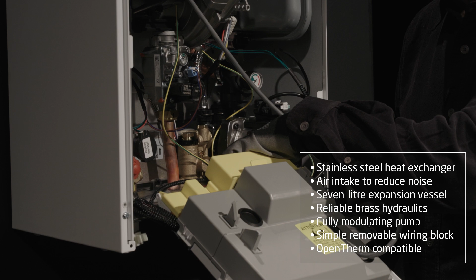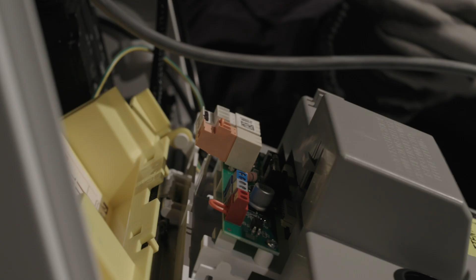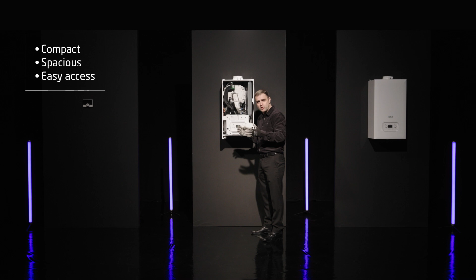And one really nice feature is if I'm in a tight cupboard, if access is a problem, I can take this wiring block out, wire it in a more convenient location, and then just pop it back in. I can do the same for the 240 volt controls. And of course I've got low voltage controls, and it is fully OpenTherm compatible, certified OpenTherm. And of course it's got weather comp in there as well. So it's got all the latest tech, and it's a nice compact boiler, but it's spacious, no problems accessing anything.